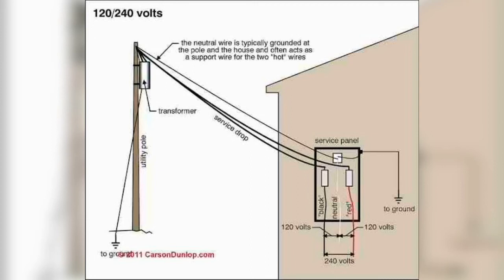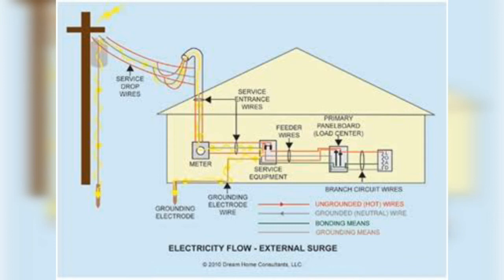When a fault occurs, current flows via the ground conductor back to the electrical panel. If a TN-C or TN-C-S earthing system is in use, all the neutrals are connected to the ground at the joint of the output and the supply meter. See the earthing system in the schematic below. So a hot to grounded fault of appliance electrodes becomes a hot to neutral fault, practically a short circuit. A large current flows and the tripping of an MCB, meaning miniature circuit breaker, is possible. Also a GFCI acts first, cutting power and making everything safe.